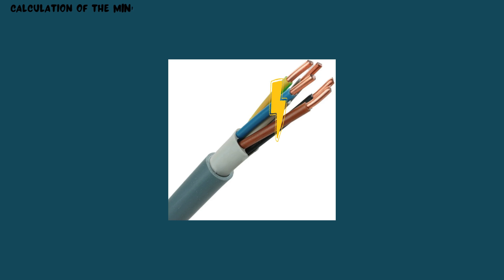When a short circuit occurs, the amount of current flowing through the conductor might surpass the nominal current during short periods of time, heating up the insulator. It is necessary to verify that the proposed cross-section can withstand the maximum short-circuit current.